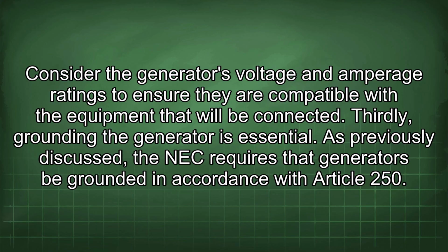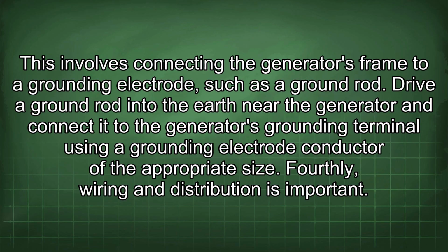Thirdly, grounding the generator is essential. As previously discussed, the NEC requires that generators be grounded in accordance with Article 250. This involves connecting the generator's frame to a grounding electrode, such as a ground rod. Drive a ground rod into the earth near the generator and connect it to the generator's grounding terminal using a grounding electrode conductor of the appropriate size.